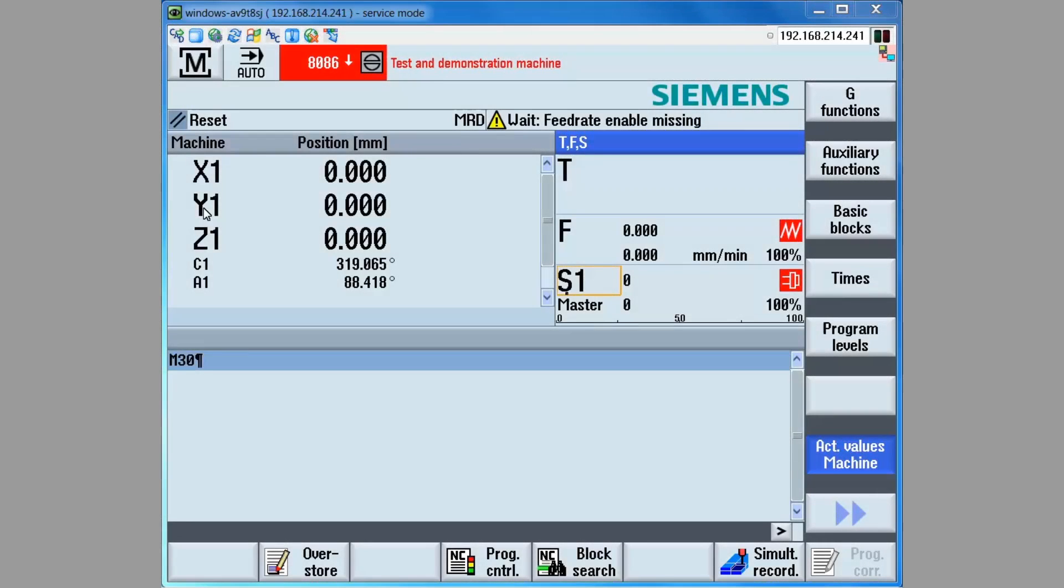Please note that the processes in this video require axis movement. Therefore, all necessary safety precautions must be taken into account before executing any of the described tests. The measurement process moves the relevant axis at an offset velocity while a set point frequency band is inserted to the drive for the measurement. The user must observe the testing conditions for possibly too high of an amplitude or offset velocity and can abort the test if necessary.